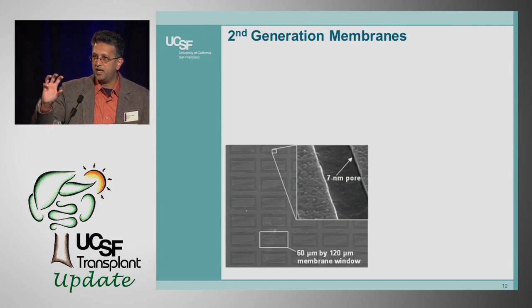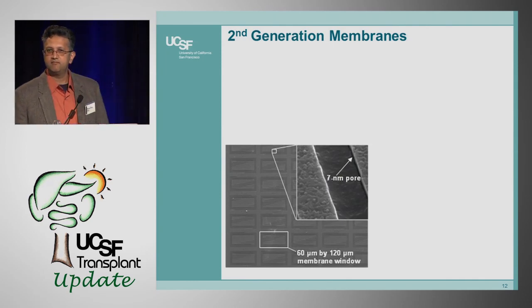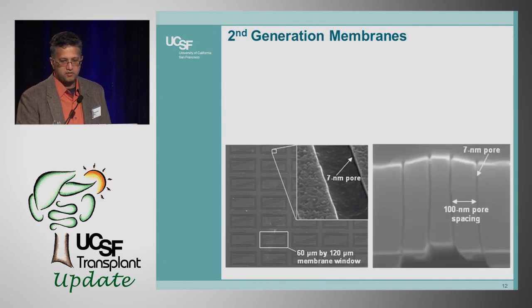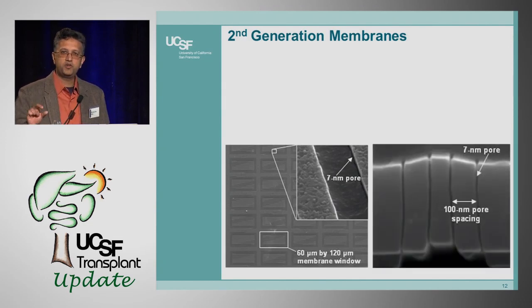The hydrodynamic diameter of the albumin molecule is about 7 nanometers, so if we pick something around that, and we've confirmed this, we can get very little or no albumin leakage. In cross-section, we have pores that are very straight and very precisely controlled, and the membrane thickness here is about 0.5 microns. Contrast that to the 30, 40 micron thickness of conventional hollow fiber membranes.